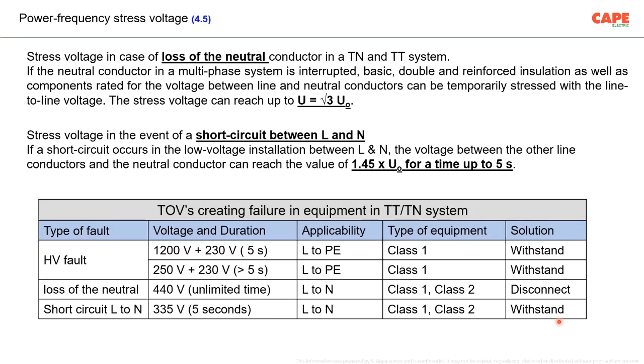So if we leave the second case, the loss of neutral, in an industrial environment or in a critical environment like a hospital or a data center or BMS or instrumentation system, you should ensure that equipment operating with 230 volt or 400 volt is able to withstand 335 volt between line to neutral for 5 seconds. It must be able to withstand, no compromise on that. Similarly, the second one, for example, 1200 volt plus 230 volt between line to earth, applicable for a class 1 equipment, your equipment must be able to withstand. You also should ensure that your design is made in such a way that the voltages are limited within this tolerable voltage and duration which I have mentioned. If the design is not taking care of it, of course more voltage comes and your equipment will be in trouble.